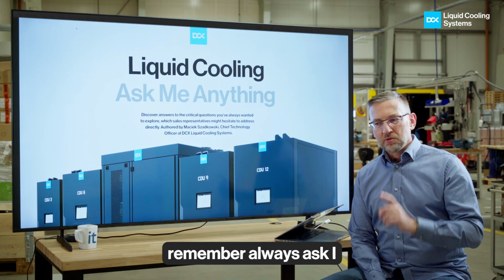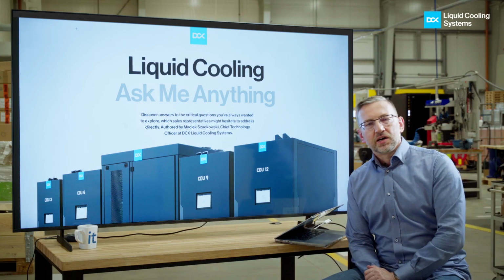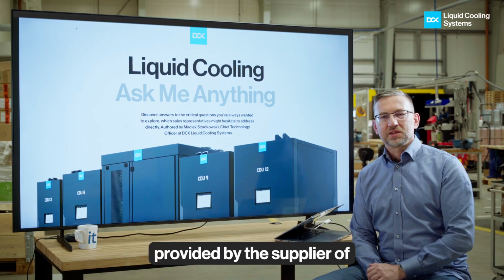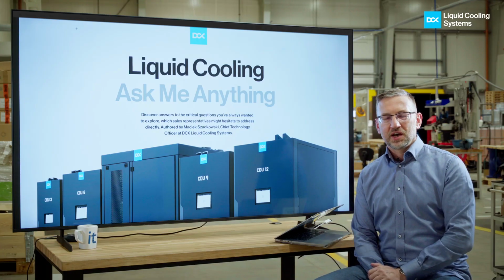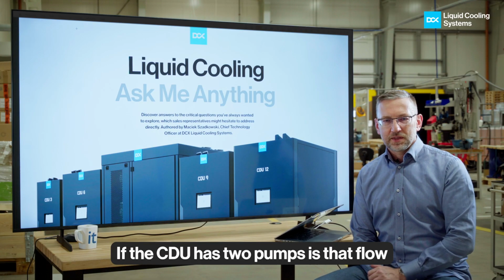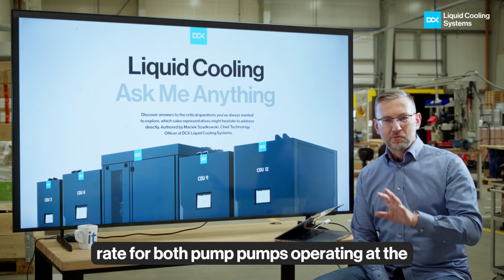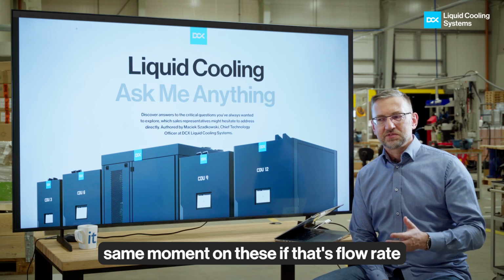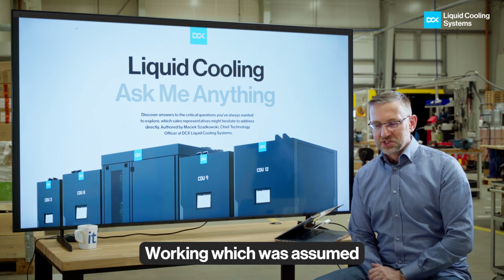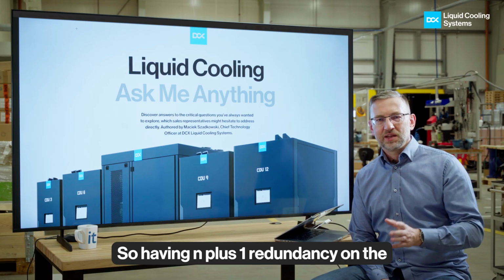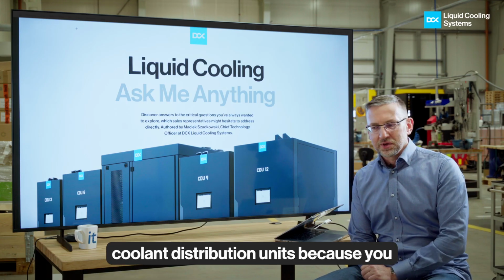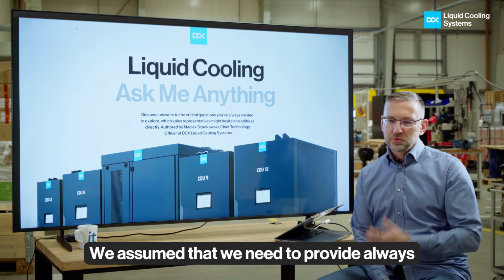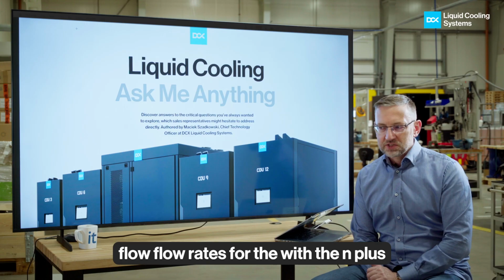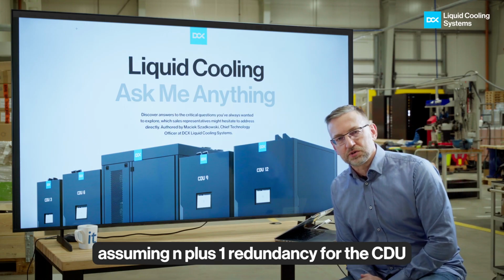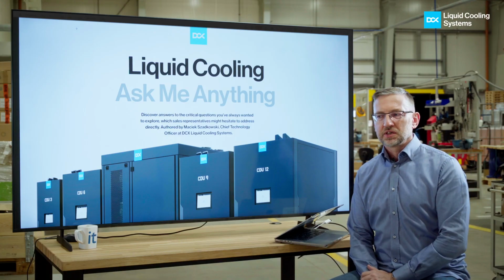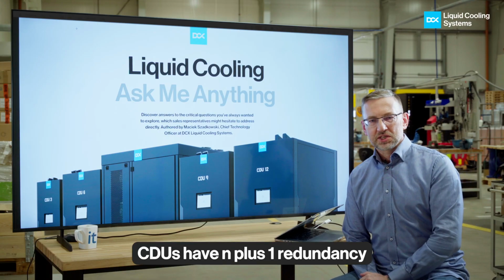And please remember, always ask, I cannot stress that enough, whether the flow rate provided by the supplier of the coolant distribution unit assumes N+1 redundancy. If the CDU has 2 pumps, is that flow rate for both pumps operating at the same moment? Or is that flow rate assumed for only 1 pump operating, so having N+1 redundancy on the coolant distribution units? Because different vendors provide different numbers. We assumed that we need to always provide flow rates assuming N+1 redundancy for the CDU. So 1.5 liters per minute, assuming that all the CDUs have N+1 redundancy.